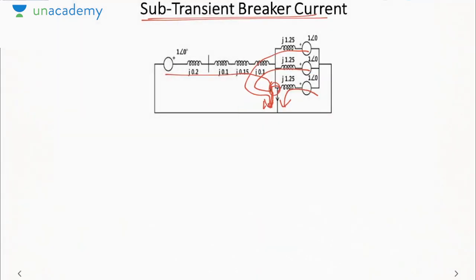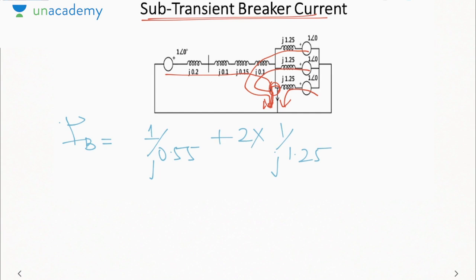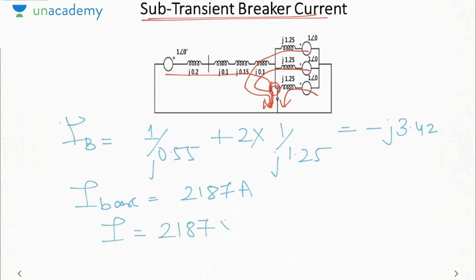So whenever we are calculating the subtransient breaker current, we will take the generator current, that is 1 by j0.55. We will take the current of two motors and not all three motors. So how much will this come out to be? Minus j3.42. The base current will remain the same because breaker B also lies in region number 3, 2187 ampere. So I will be 2187 into 3.42, so it will be 7479.5 ampere. That will be your subtransient breaker current, or the current going into the breaker in the subtransient region.